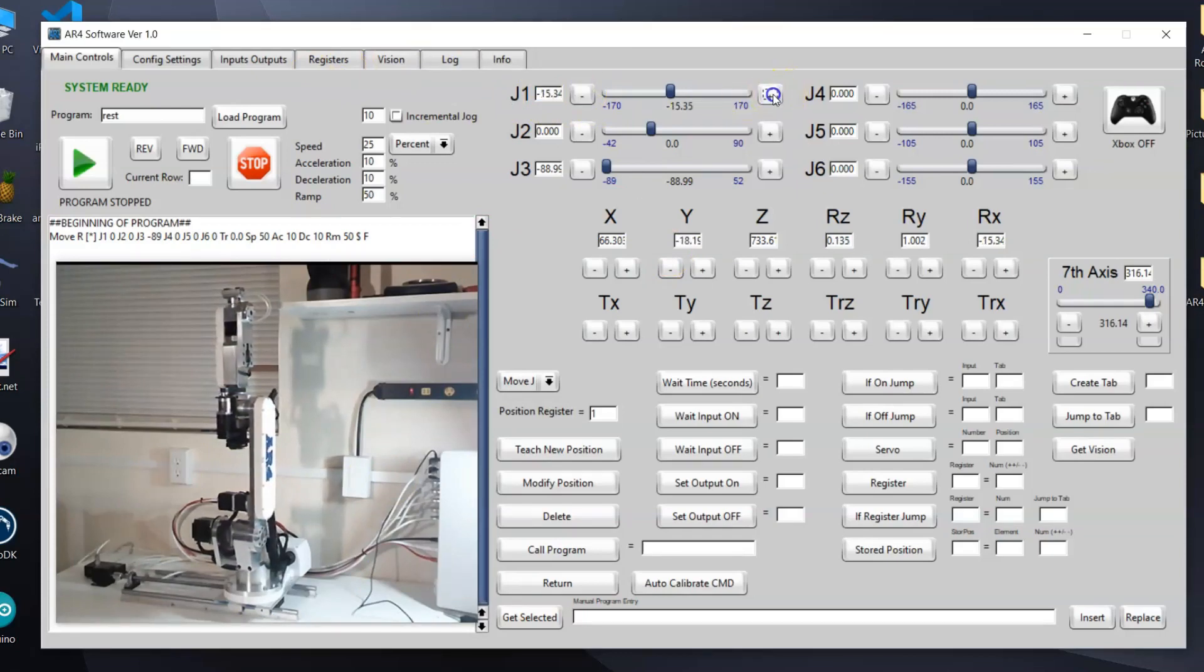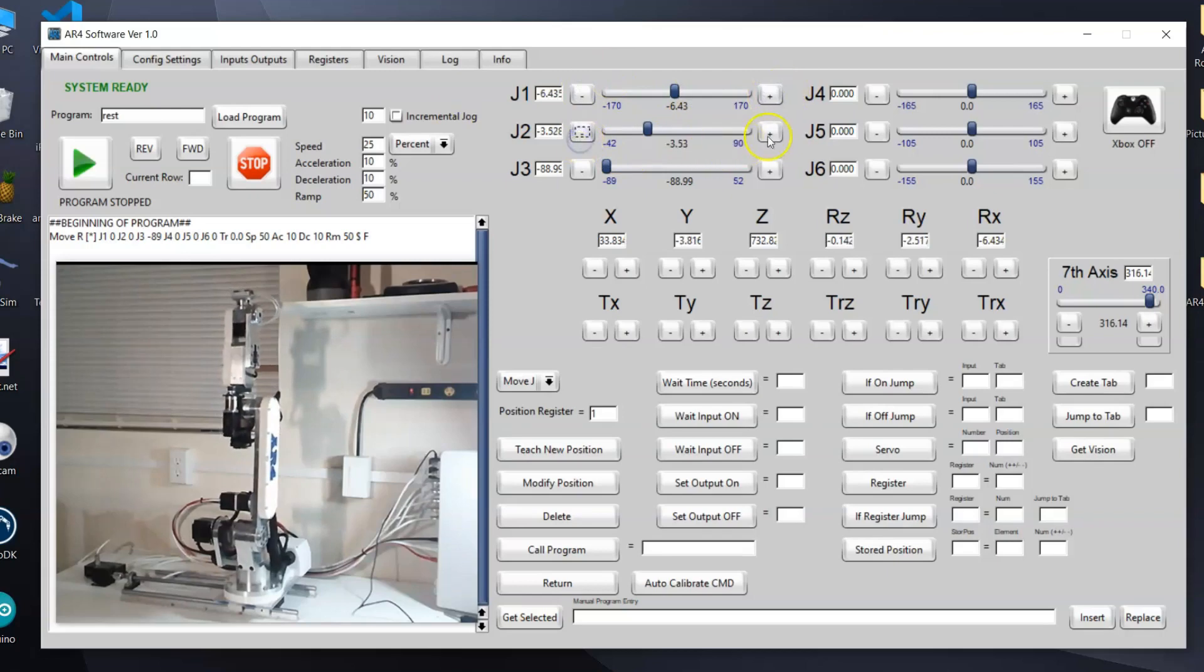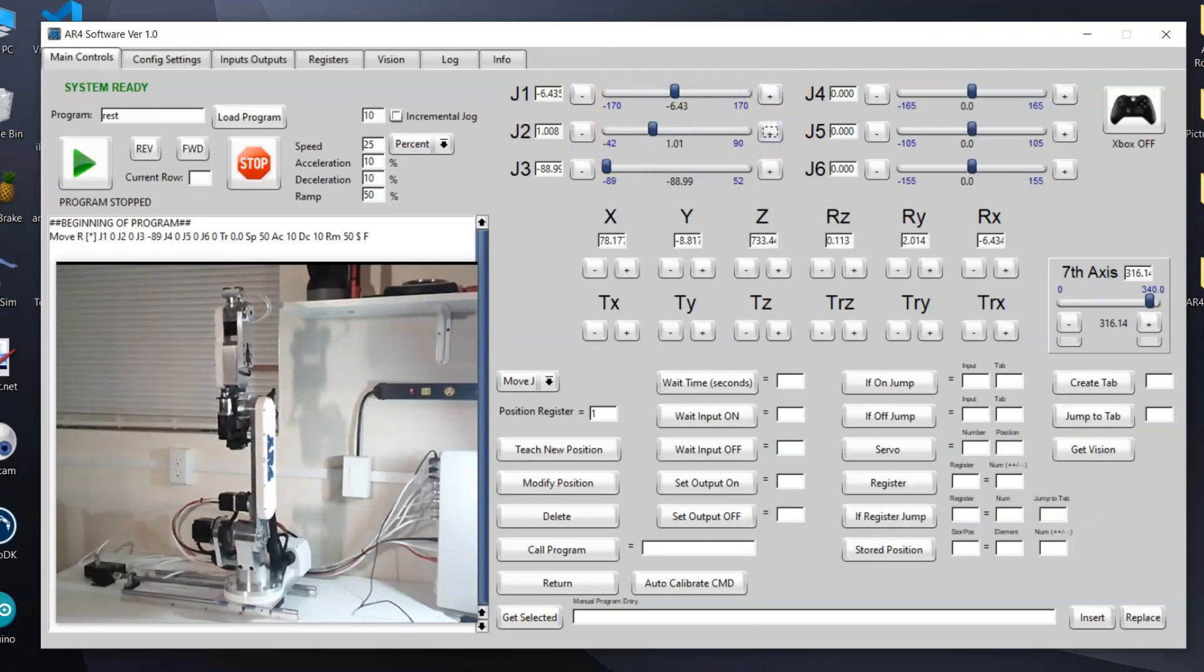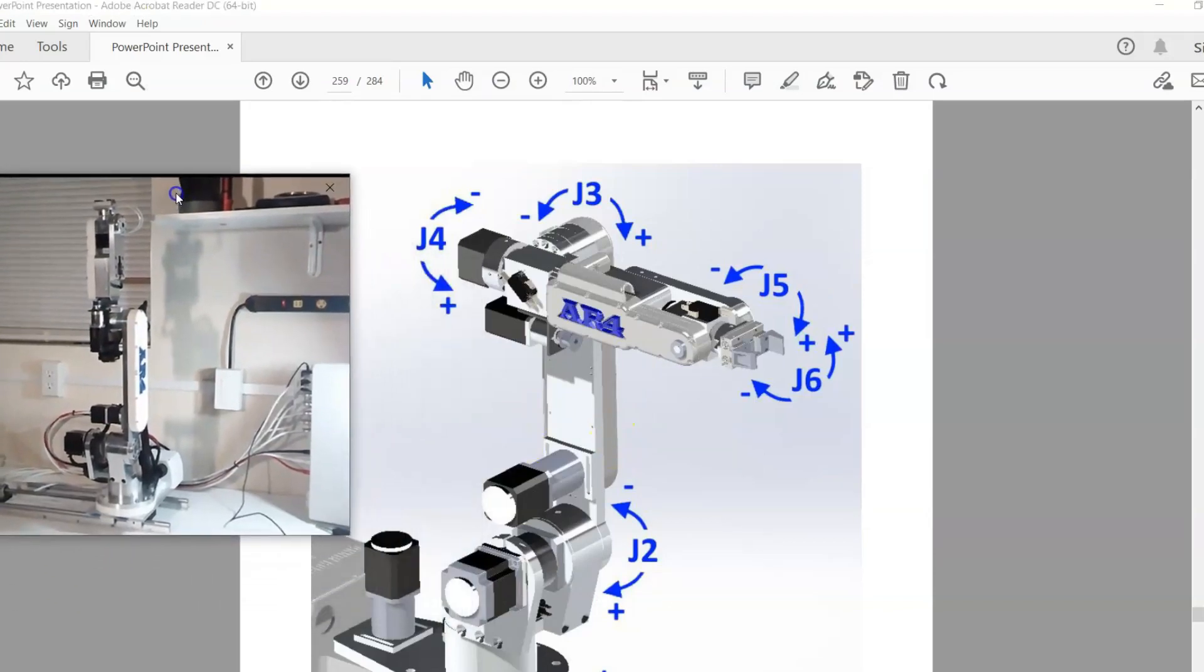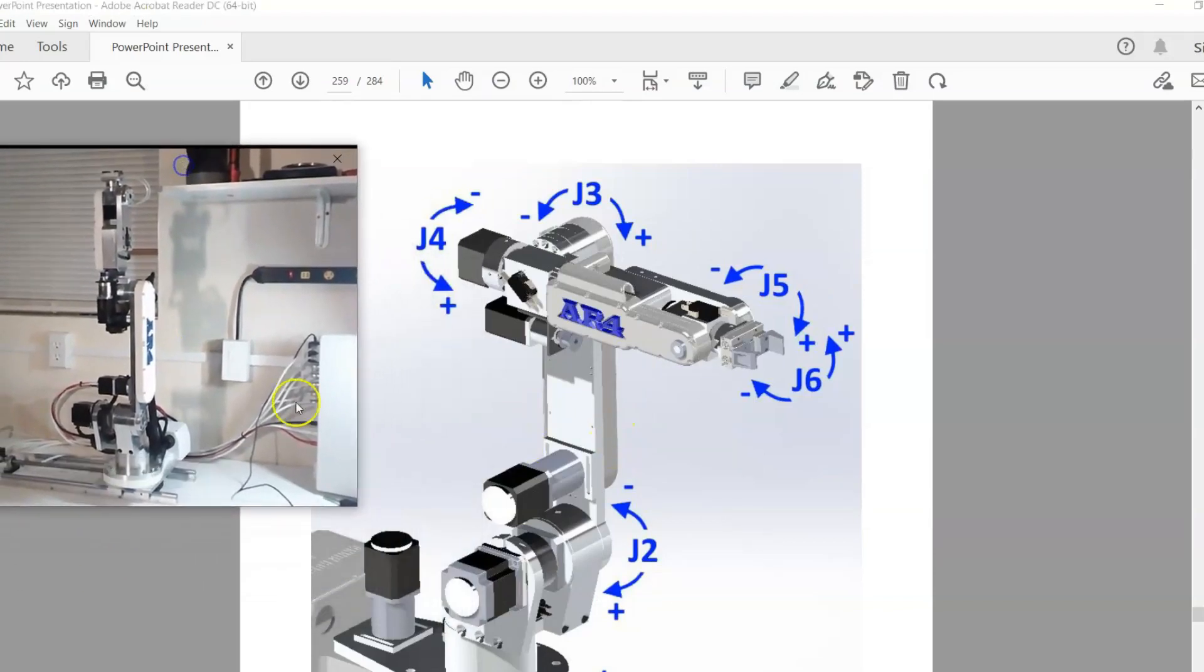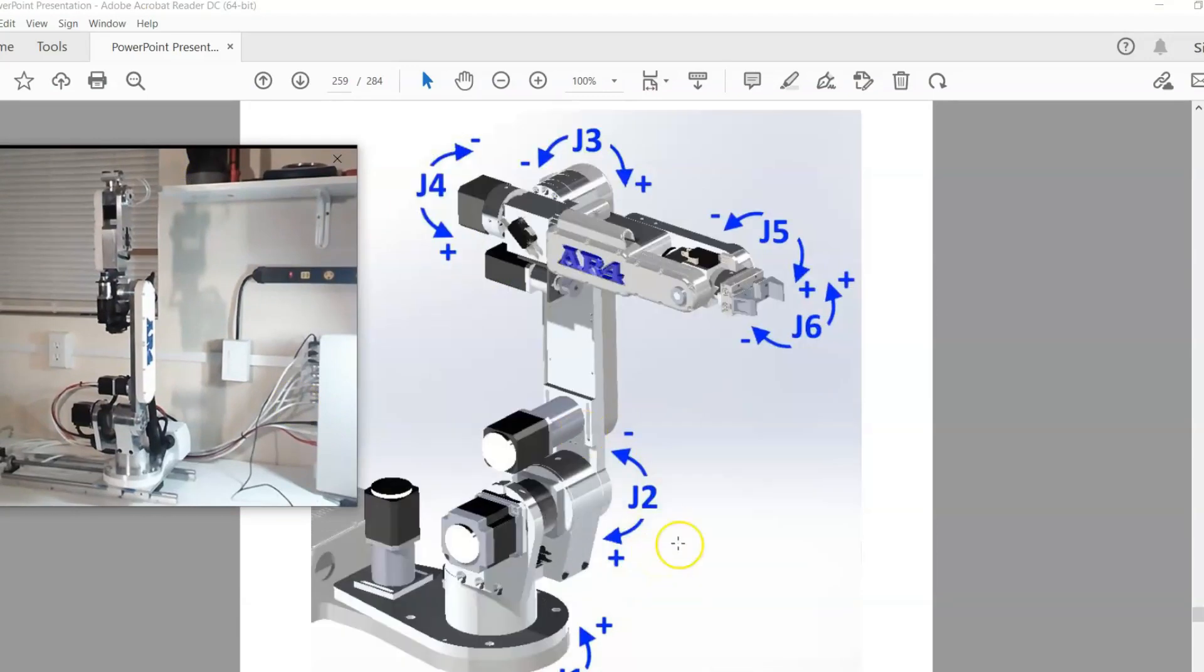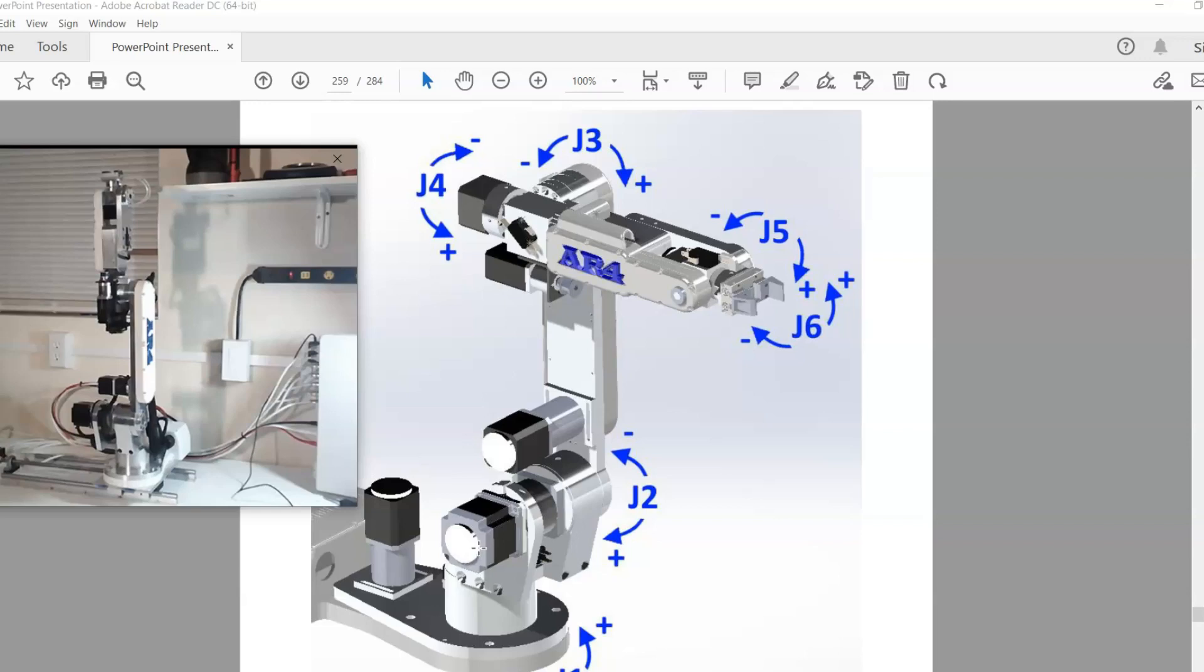You can see that if I click on a direction you can see the robot is jogging as expected. I just want to make sure that when I'm jogging the robot that I follow this image in the startup section to make sure that positive and negative that each joint is jogging in the correct direction.